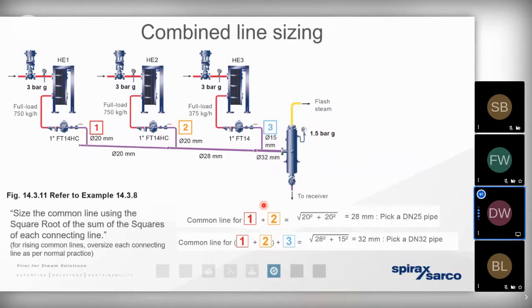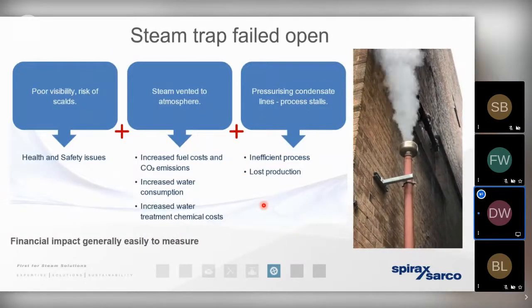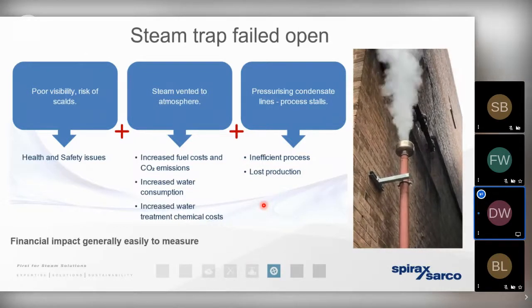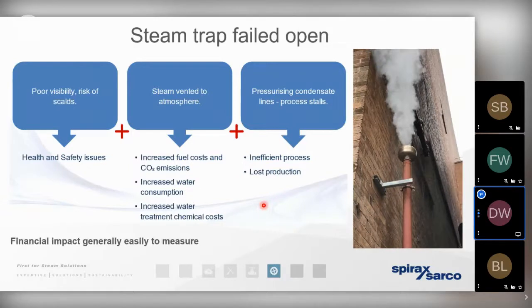So when a steam trap has failed in the open position, then steam is going to pass across the trap. It's going to become mixed in with the condensate, and it's going to be vented away at some point, typically up a steam vent, as you can see over towards the right-hand side of the screen. The problem is that lost steam is representative of a significant loss of energy. And not only are we losing the energy, we're failing to recover the condensate that's a byproduct of heat exchange. So it can be difficult to spot this unless we're specifically keeping our eyes open or checking our steam traps periodically. But the financial impact of a failed open steam trap is very, very easy to calculate or quantify.